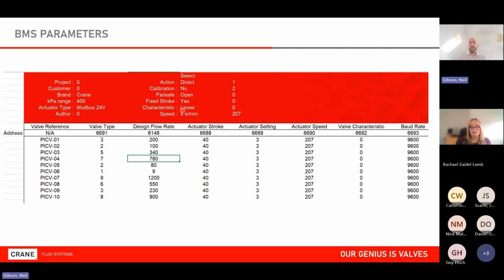I can select what my valve operation is. These are a series of drop-down boxes. If I change it from direct to reverse, it changes the bit here, and I can generate a new output. So this is my actuator setting under address 6689. Speed, valve characteristic, the baud rate, all of these things I can configure and already have preset, in the sense that I can provide all of this information without having to look through the Modbus tables individually.